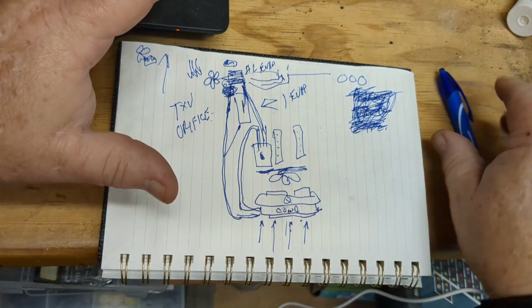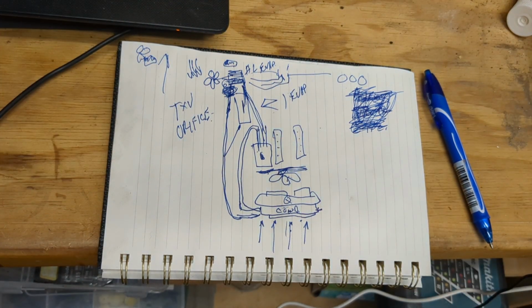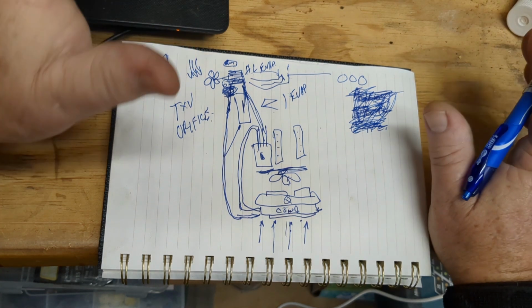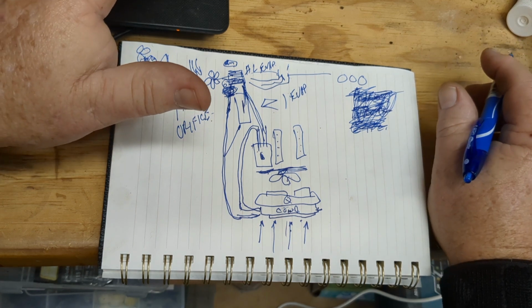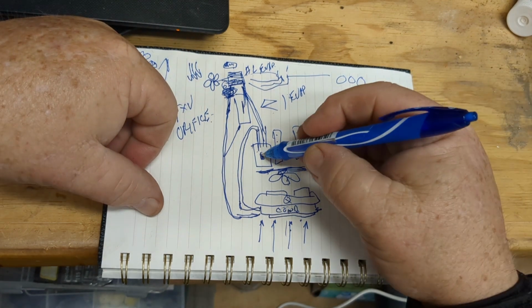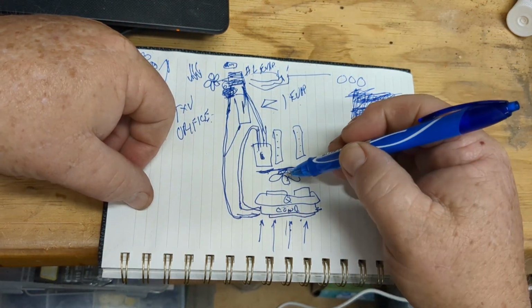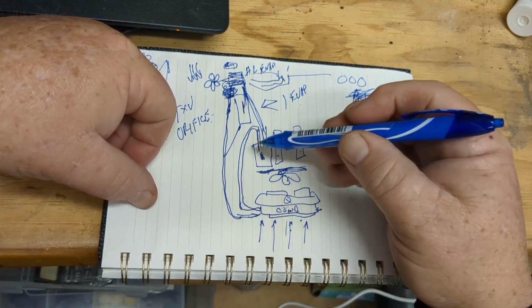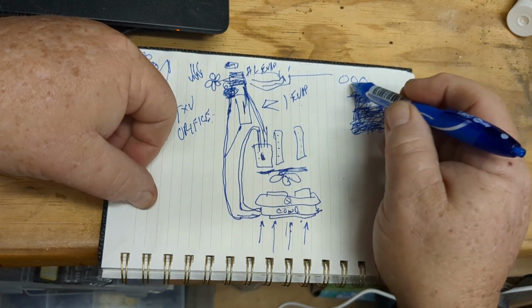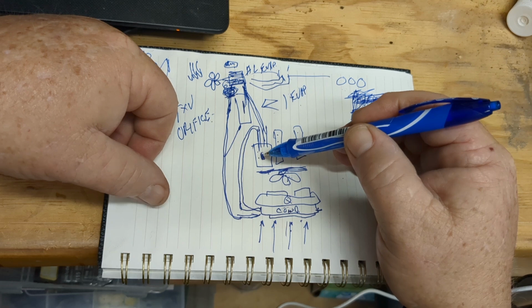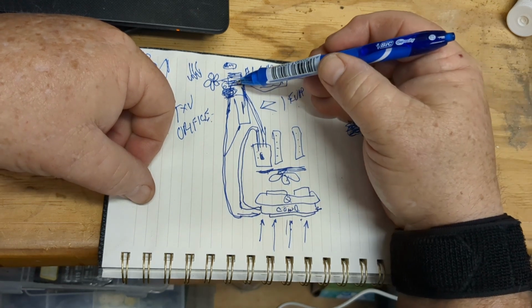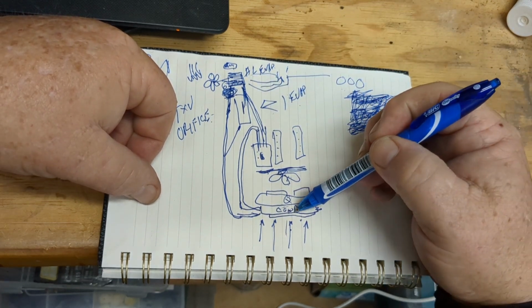Everything's got to work in symphony. And the really only way to know your baseline diagnosis is that everything has to be clean, and that applies to household air conditioners too. If all the components are functioning, you've got fan, compressors functioning, controls are working correctly, the next thing you're going to have to check is occlusion here and occlusion here.